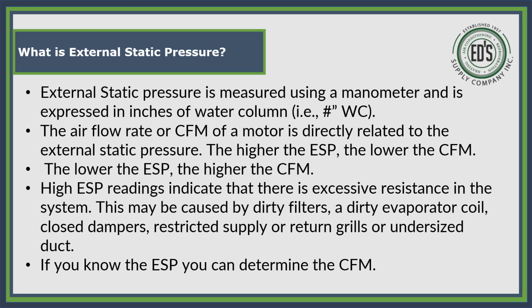External static pressure is measured using a manometer, and it's expressed in inches of water column, i.e. WC. The airflow rate, or CFM, of a motor is directly related to the external static pressure. The higher the external static pressure, the lower the CFM. The lower the external static pressure, the higher the CFM. High static pressure readings indicate that there is excessive resistance in the system. This may be caused by dirty filters, dirty evaporator coils, closed dampers or closed grills, restricted supply or return grills, or undersized ductwork. If you know the external static pressure, then you can determine what the CFM is.